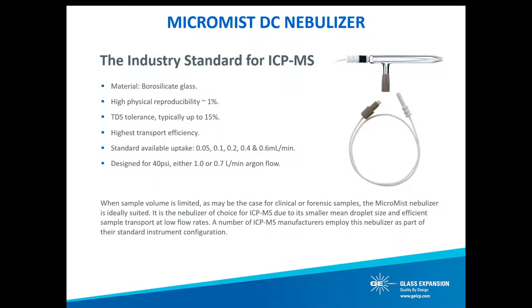Now let's talk about the MicroMist nebulizer. The MicroMist is our most popular nebulizer for ICP-MS applications and the standard nebulizer configuration for many ICP-MS manufacturers, due to its excellent transport efficiency and precision at low flow rates. For example, the 50 microliter per minute MicroMist has a 50% efficiency, therefore injecting 25 microliters per minute into the plasma. On the other hand, a standard high-flow 2 mils per minute nebulizer has approximately 2% transport efficiency, resulting in about 40 microliters per minute of sample injected into the plasma.